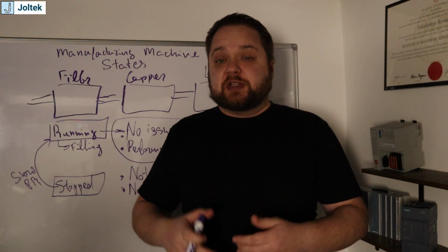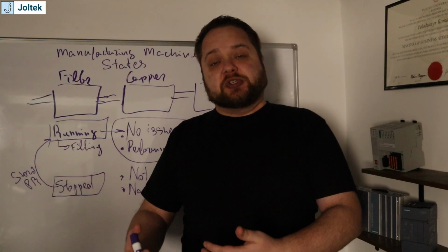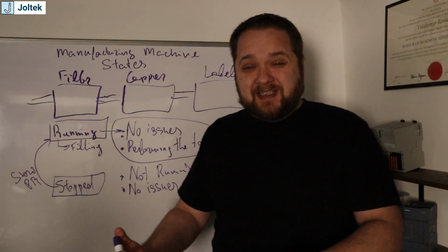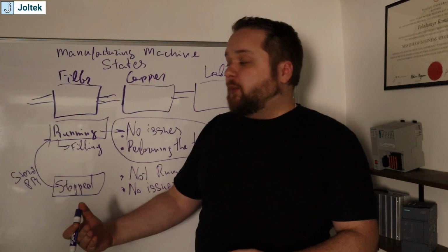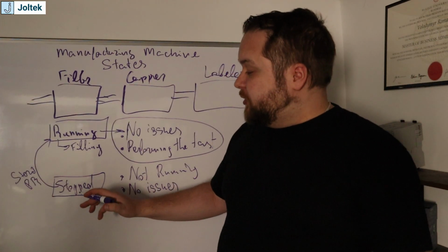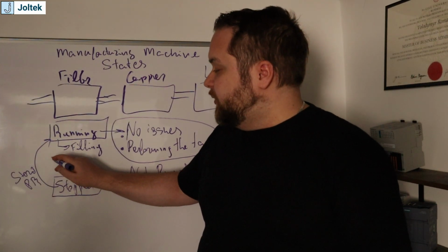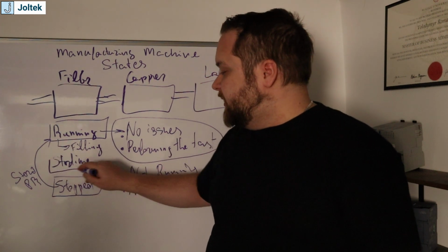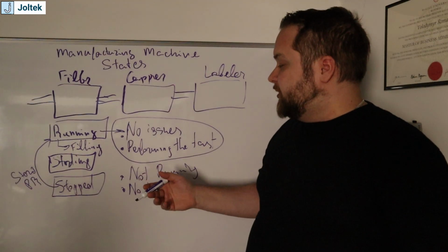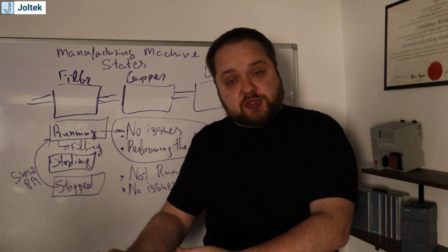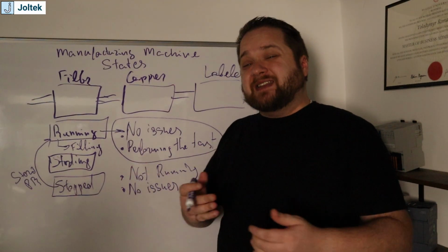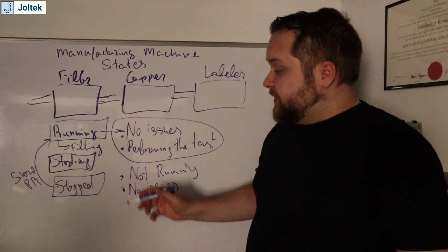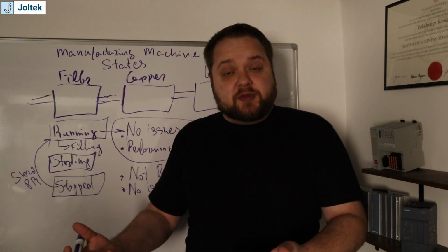There's going to be machines that will have different control systems for your PIDs before they start operating. So in this case, you can also have a state in between, which is called starting, right? The starting state does not necessarily mean that the machine is producing product, but it does mean that it is getting there. So this transition, again, do you care about this transition?